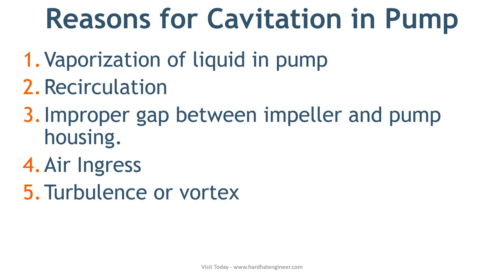The fourth reason is air ingress. If the pump is running at lower than atmospheric pressure, there is a chance of air ingress from any poor joint, and this air will create the same cavitation effect in the pump. The fifth and last reason is turbulence in the flow. Turbulence or vortex can occur in flowing liquid due to various design-related reasons in the piping system. If this vortex forms near the pump suction, it will have the same effect as low NPSH. There may be other reasons, but these five are the major contributors.